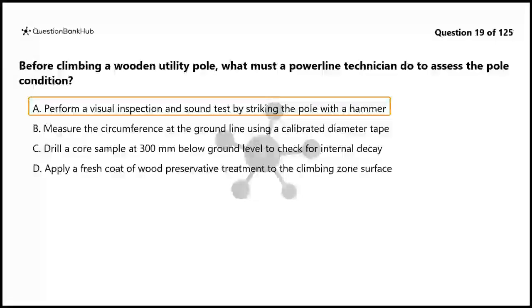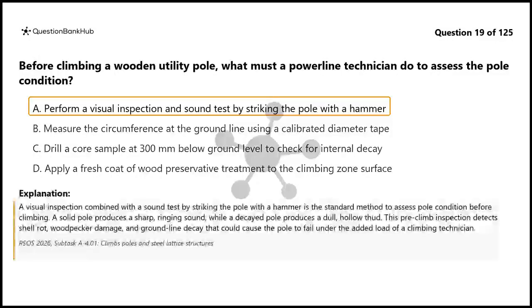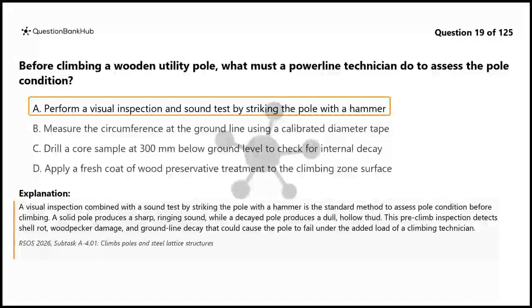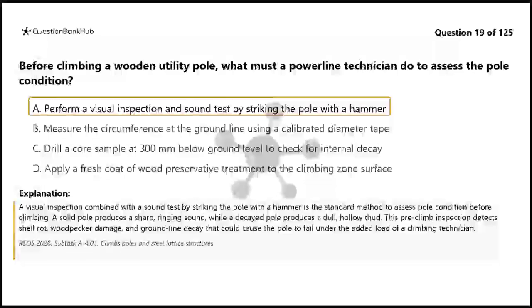The correct answer is A. A visual inspection combined with a sound test by striking the pole with a hammer is the standard method to assess pole condition before climbing. A solid pole produces a sharp, ringing sound, while a decayed pole produces a dull, hollow thud. This pre-climb inspection detects shell rot, woodpecker damage, and ground line decay that could cause the pole to fail under the added load of a climbing technician.